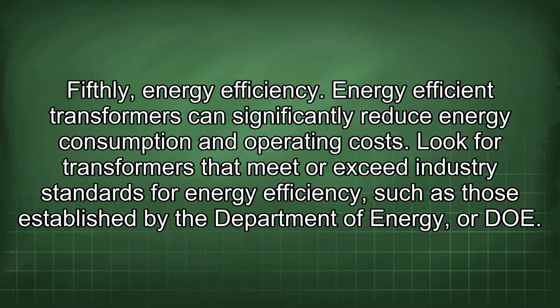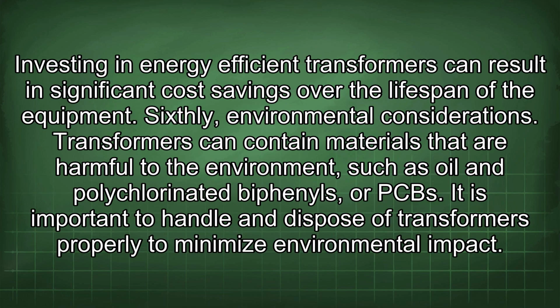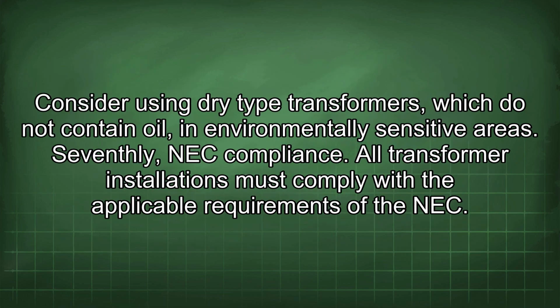Fifthly, energy efficiency. Energy-efficient transformers can significantly reduce energy consumption and operating costs. Look for transformers that meet or exceed industry standards for energy efficiency, such as those established by the Department of Energy, or DOE. Investing in energy-efficient transformers can result in significant cost savings over the lifespan of the equipment. Sixthly, environmental considerations. Transformers can contain materials that are harmful to the environment, such as oil and polychlorinated biphenyls, or PCBs. It is important to handle and dispose of transformers properly to minimize environmental impact. Consider using dry-type transformers, which do not contain oil, in environmentally sensitive areas.